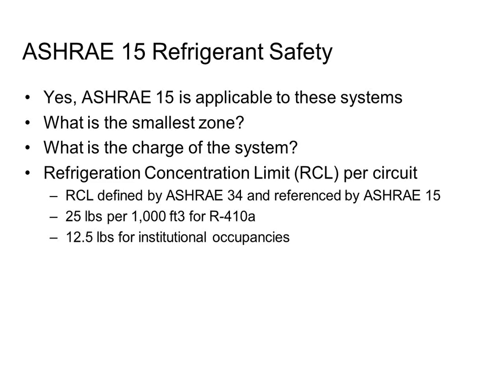If my smallest zone is a 10 by 10 office and it has an evaporator in it, and let's say the ceiling height is 10 feet because that makes the math easy for me, that has 1,000 cubic feet. I can have a maximum VRF system of 25 pounds. If I install one that's 29 pounds, I can't do it. I'd have to not install that system or I've got to change something, right? And we'll talk about things we can change in a second here.